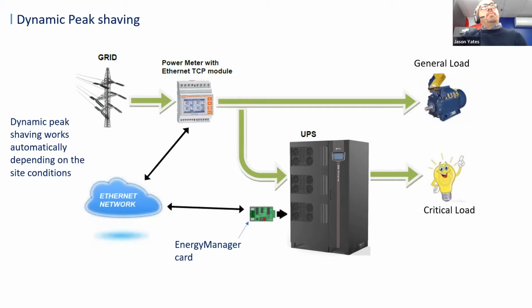Just to explain and expand upon this a little further, this would be a typical dynamic peak shaving application. As you can see there, you've got the incoming grid onto a site where you have power metering. This power metering is interconnected with the communication cards within the UPS system. You've got critical load connected to the output of the UPS system, so battery backup is provided for that load. And you've also got the general site load. So as the load increases, the UPS system can share a portion of that load onto its internal batteries instead of overloading the main incomer.